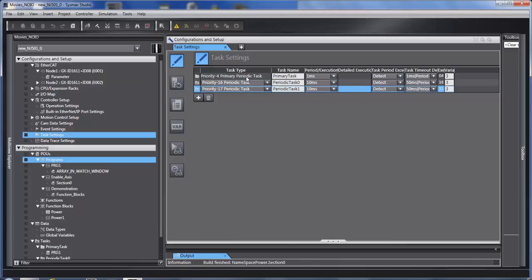If your EtherCAT is refreshing, if this task is running at one millisecond, your EtherCAT is refreshing at one millisecond. If it's half a millisecond, then your EtherCAT refreshes at half a millisecond. All of your motion code should be in this task.